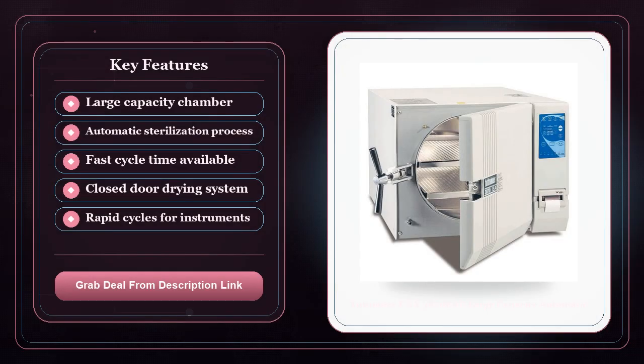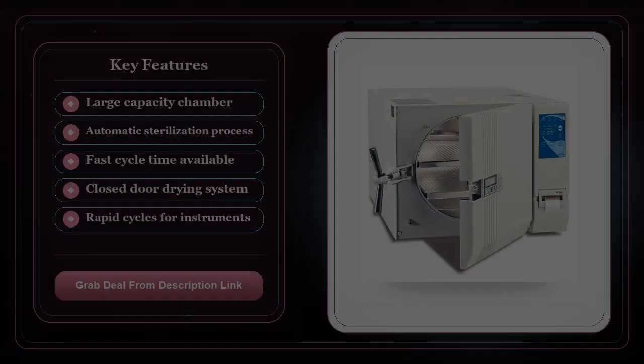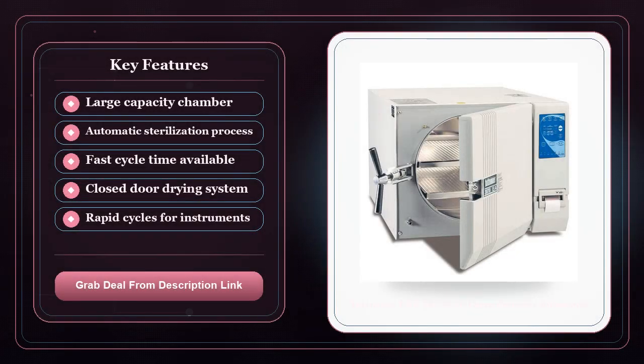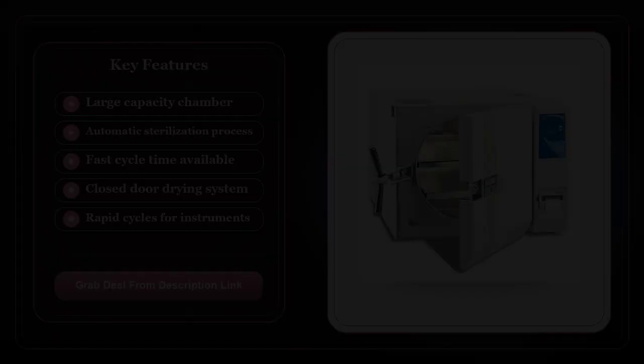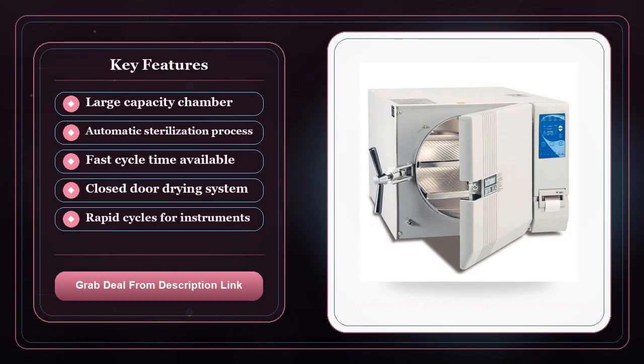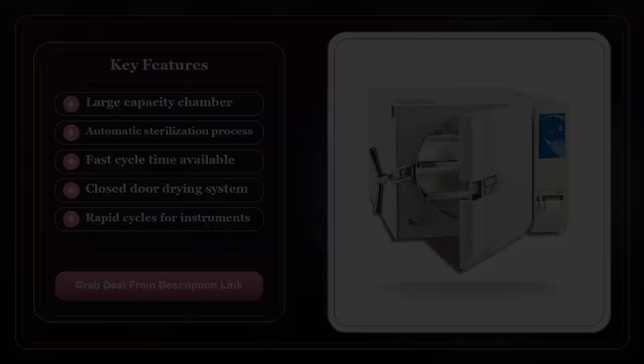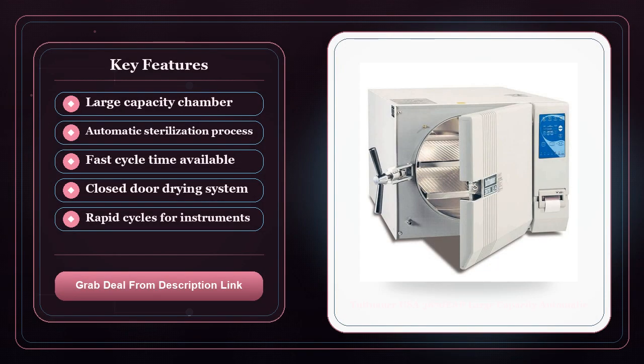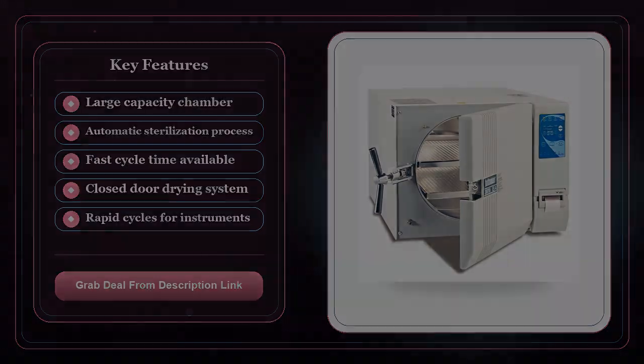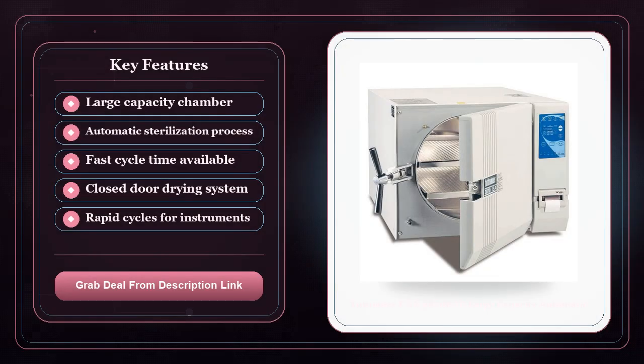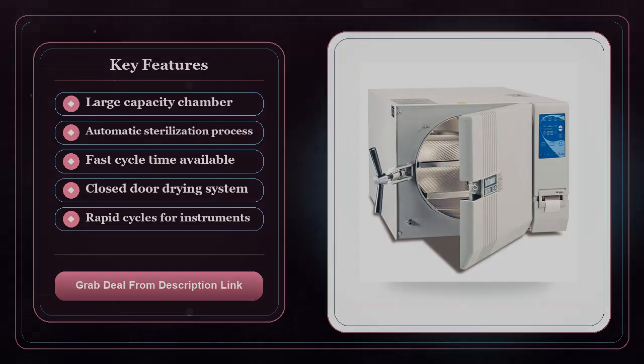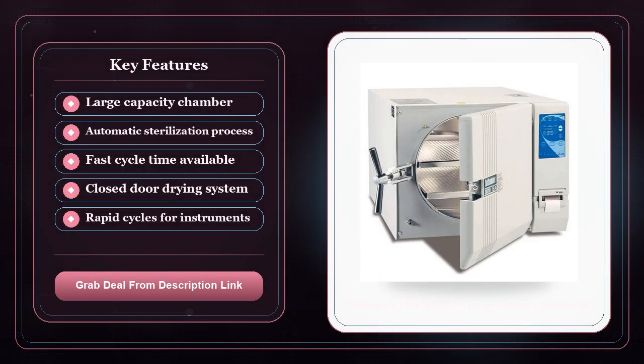Let's talk value beyond the specs. The real money saver here is the reduction in repeat cycles. With a smaller autoclave, you often end up running multiple short cycles to get through the day's load, which means more energy use and more wear on the machine. The 3870 EAP's ability to handle a full day's workload in fewer cycles translates to lower cumulative energy consumption and less downtime for the unit itself. Additionally, the printed cycle reports provide an audit trail that can protect you in case of an infection control investigation, something that's hard to quantify but can save you a lot of trouble.